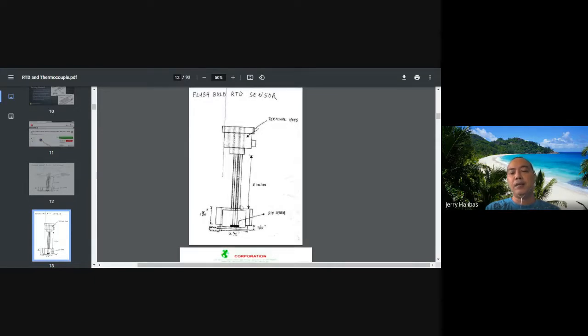In fact, it can even be customized so you can add a groove that can be opened by turning it. You can replace your sensor there by buying only the around 300 peso thin film RTD or PT100 type. You epoxy it in place, and of course you just recycle the existing wires.